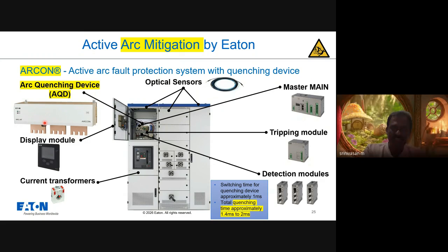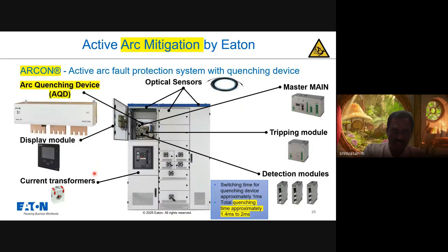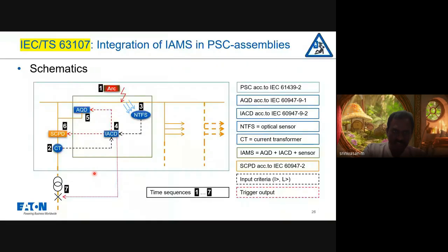This is a simple single line diagram representation of the sequence of operations. The arc is initiated. It gives a light signal, and the CT gives the current signal, which go to the IACD device. Then we give the signal to the arc quenching device, and in turn also to the short circuit protection device. At the end of the 2 milliseconds, the complete arc is quenched.